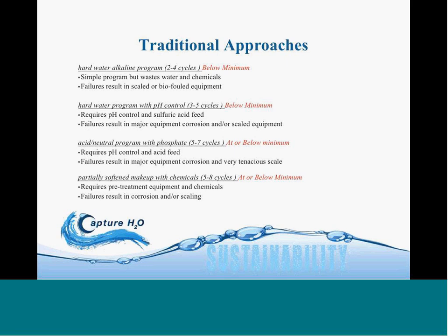So normally, what are the approaches that people take? From a water conservation standpoint, if you use straight city water, you can typically concentrate that water up between 2 and 4 cycles, which means, and LA has a new requirement where they want to see a minimum of 6 cycles. So a hard water program doesn't necessarily meet that.